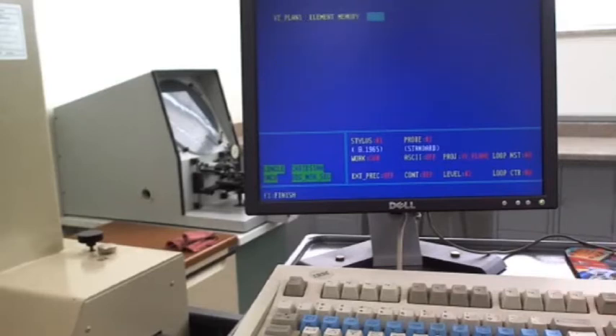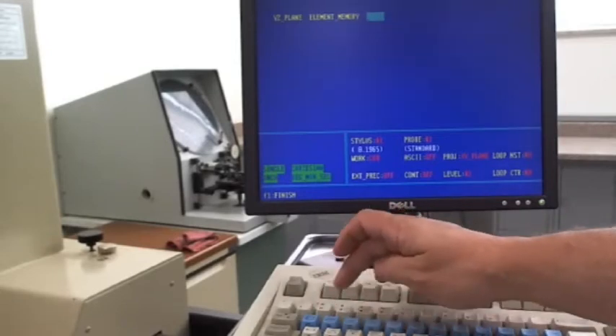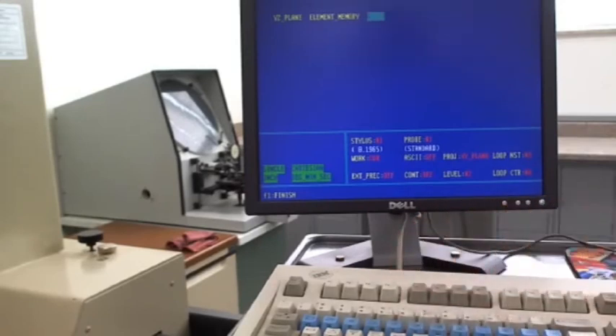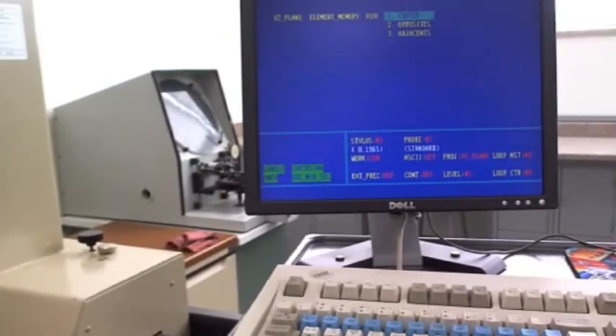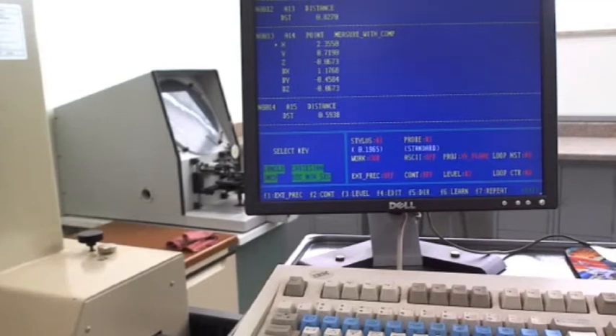We look for YZ plane, and the memory element in this case is A6, and center. For the purpose of this video, the memory element for the A hole became A10 instead of A6, but that's okay. I already typed that in, hit enter. Now I'm going to choose center, and then we get the actual dimension of 0.5938. As you'll see here, it becomes A15 as opposed to the procedure, which calls for memory A12, because we're off a little bit because of the setup of the machine. But as you can see, it does the same function.